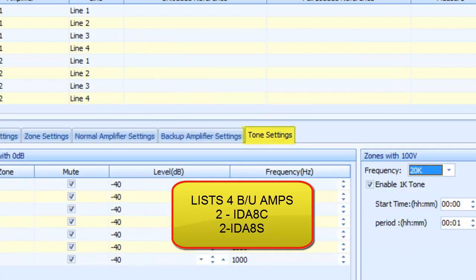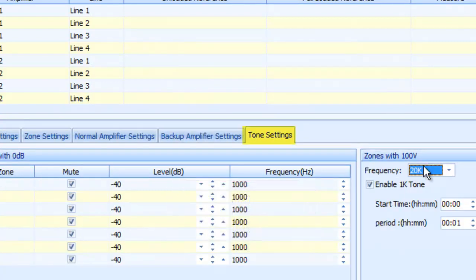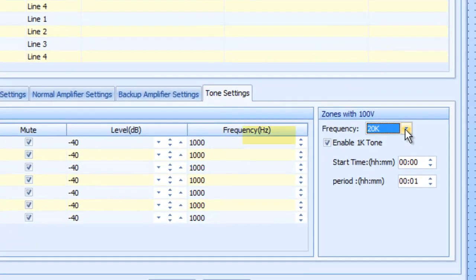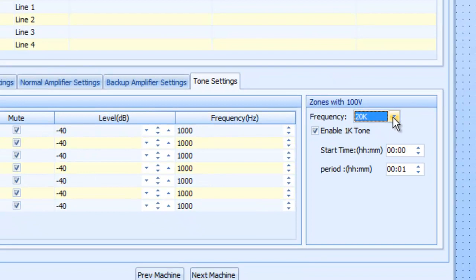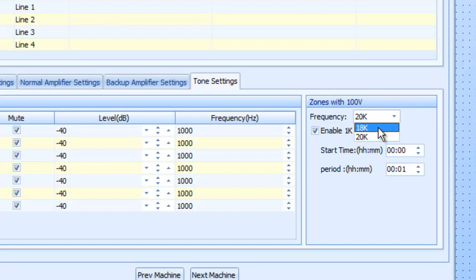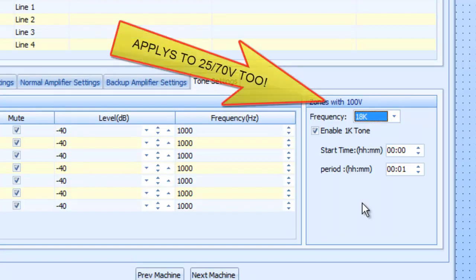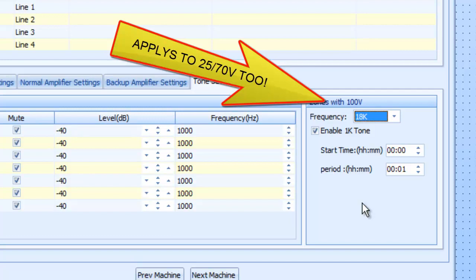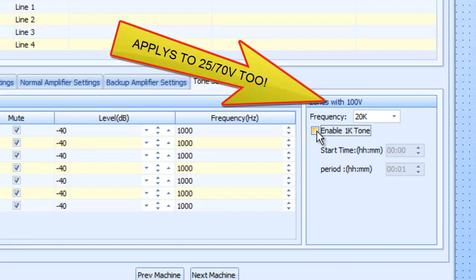Also, tone settings. The default is 20 kilohertz for the supervisory tone. If you have a digital amplifier, you can actually change this to 18K if for whatever reason that digital amplifier has a brick wall filter that's right at or just below 20 kilohertz and will not pass a 20 kilohertz sine wave. If that's the case, we have it where you can switch it to 18K. There we go.